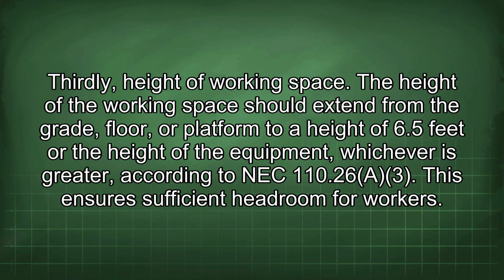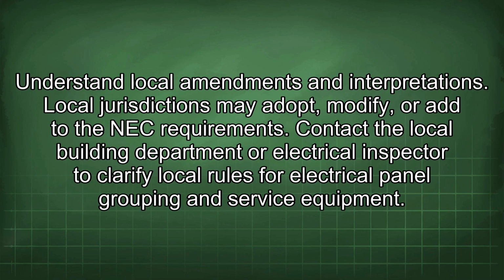Thirdly, height of working space. The height of the working space should extend from the grade, floor, or platform to a height of 6.5 feet or the height of the equipment, whichever is greater, according to NEC 110.26 A3. This ensures sufficient headroom for workers. Understand local amendments and interpretations. Local jurisdictions may adopt, modify, or add to the NEC requirements. Contact the local building department or electrical inspector to clarify local rules for electrical panel grouping and service equipment.